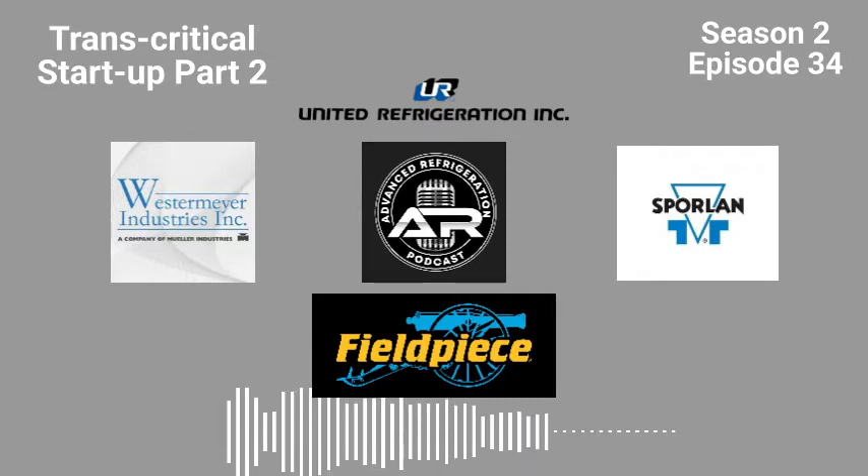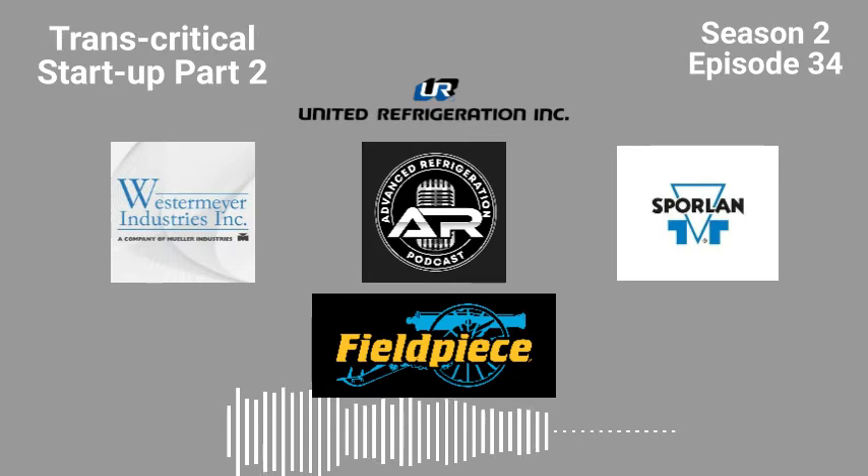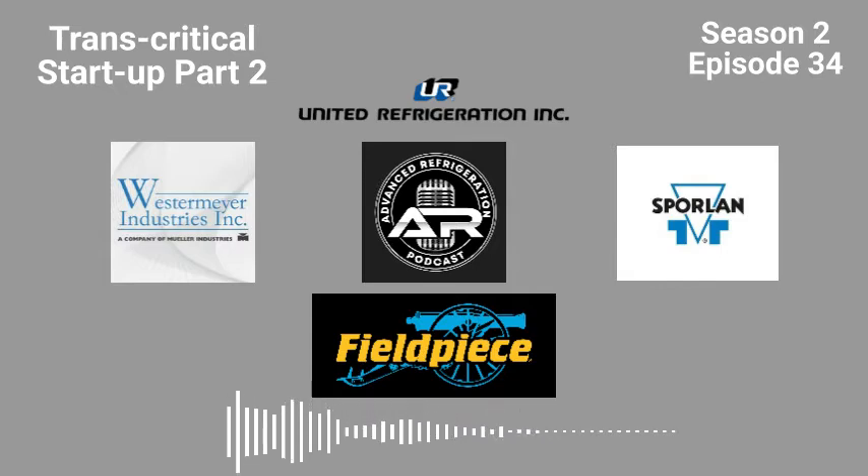What I found that works pretty good is those square crimps — they work pretty decent. Unfortunately, the ones you need are super tiny and they're a pain to fit a bunch of wires in, but they seem to hold up a lot better. We're going to bring the cases on slowly — I'm going to start with the medium temp load, bringing everything down to about 30, 40 degrees, then bring on the next case and the next. I'll watch the charge in the rack, make sure the flash tank has a ball in there, and watch my oil levels. Then I'm going to start with low temp.